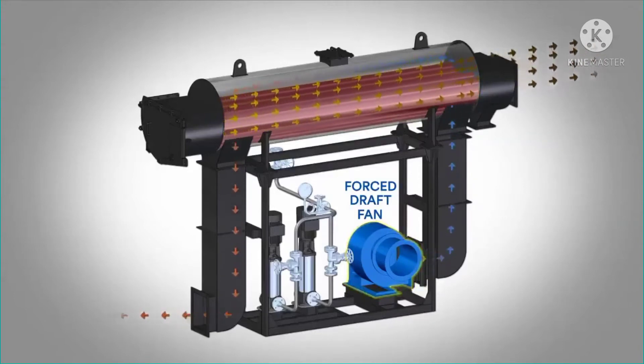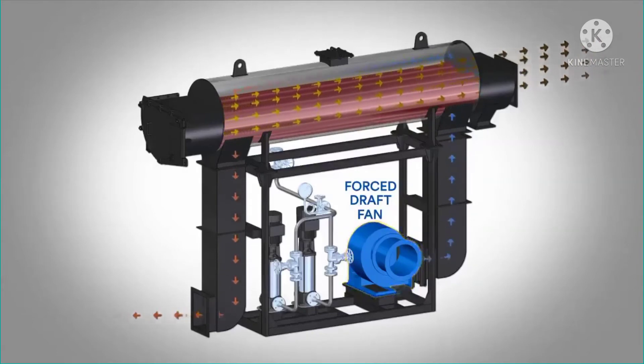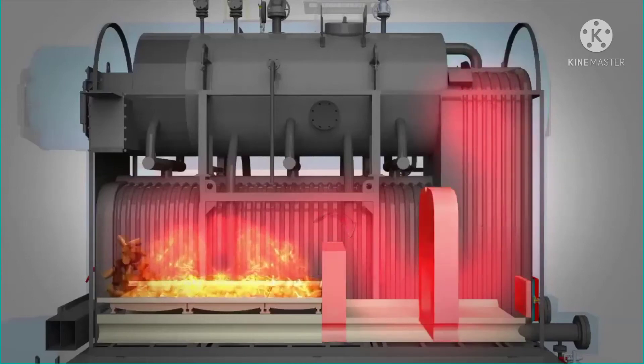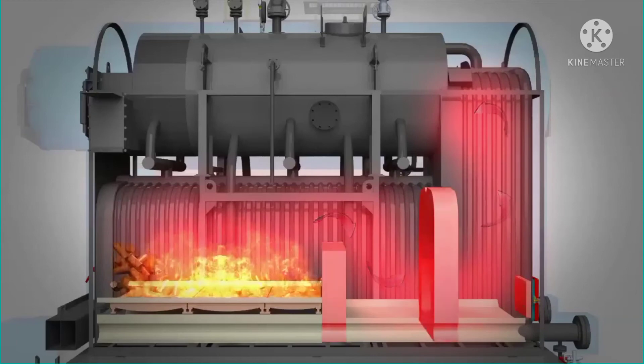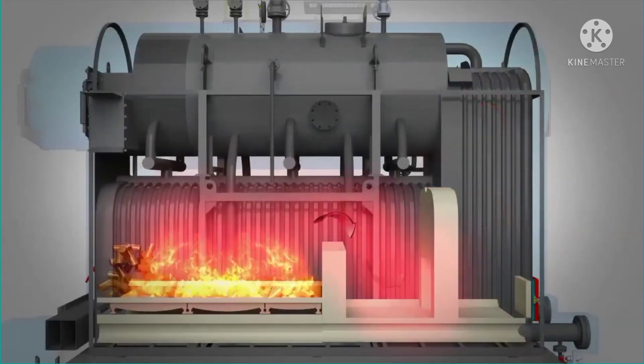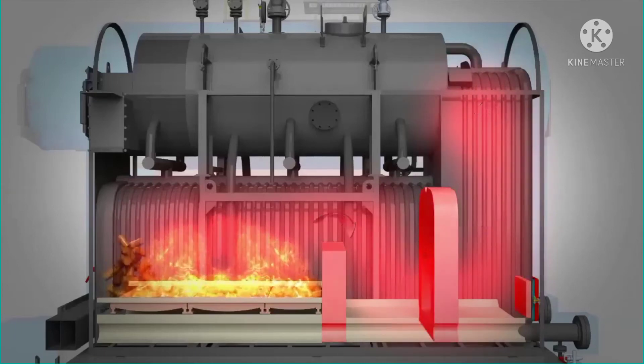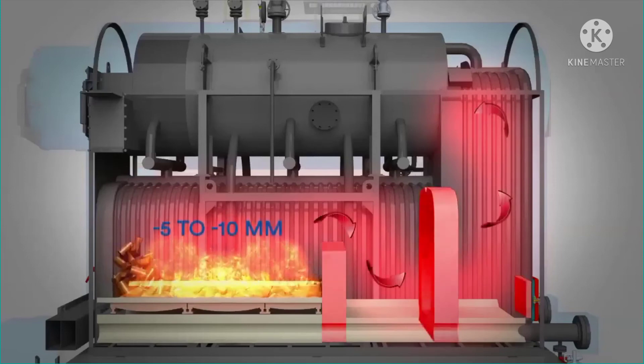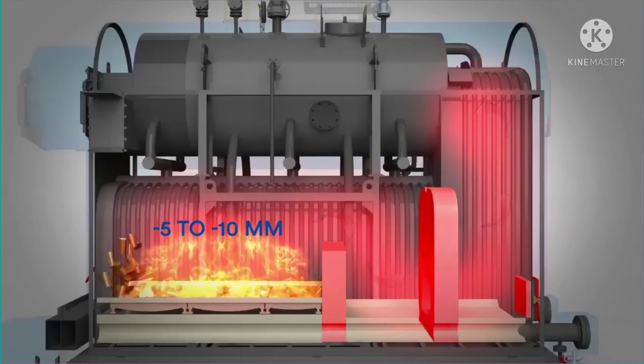When APH is used, combustion air is passed through APH and is heated up before entering the combustion chamber. The flue gases generated due to combustion of the fuel on the combustor are then taken through the membrane panel, reversal chamber, smoke tubes of the drum, HRU, and pollution control equipment by using an induced draft (ID) fan. The furnace and combustion chamber are kept at a pressure lower than atmospheric pressure, normally minus 5 to minus 10 mm of water column, by adjusting the suction of the ID fan.